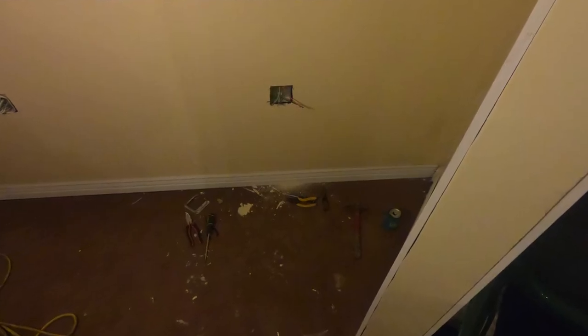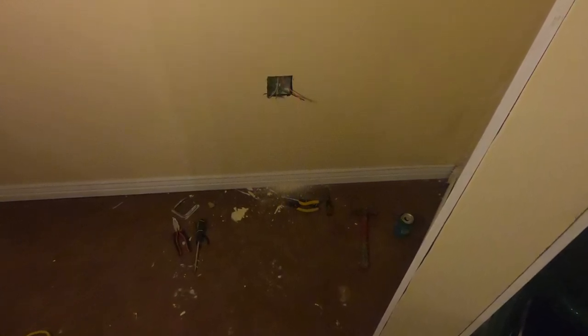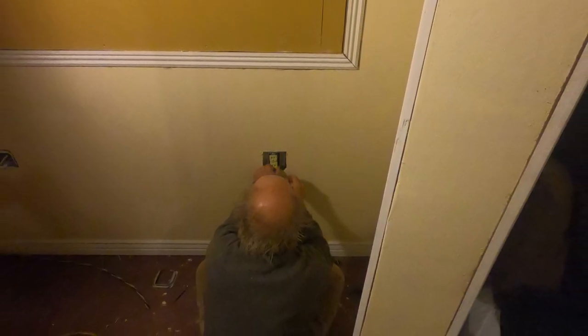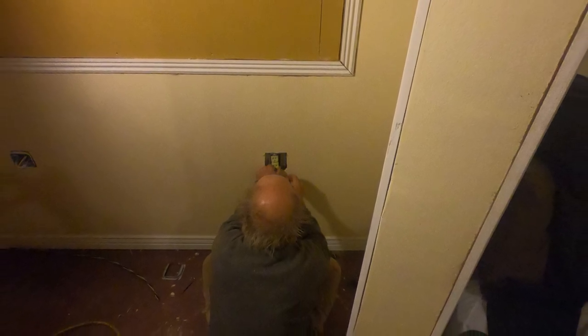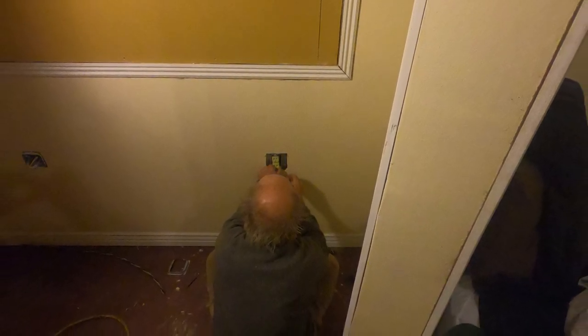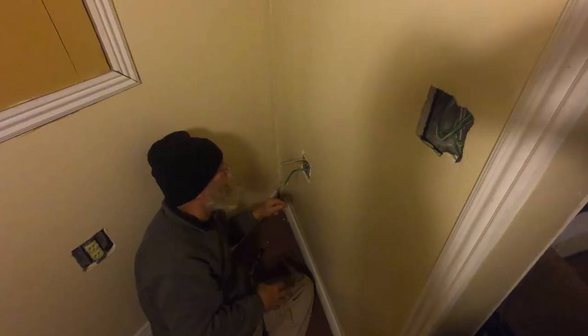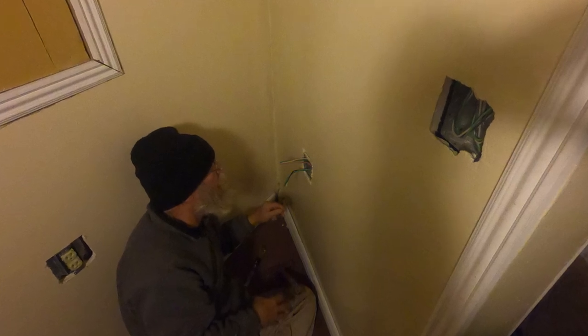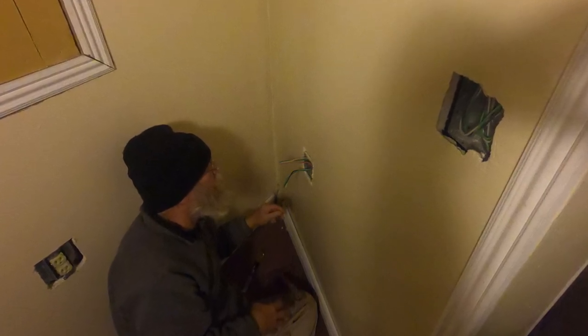With the storage area you'll see we're going through now working on it — tying all of those receptacles in to the different circuits, also tying in the lights and switches to the new lights. We've got all of that into the main panels now. Once we've got everything in place we'll go ahead and energize those independent circuits and check to make sure we have no issues — obviously a breaker tripping — and then start closing her up.